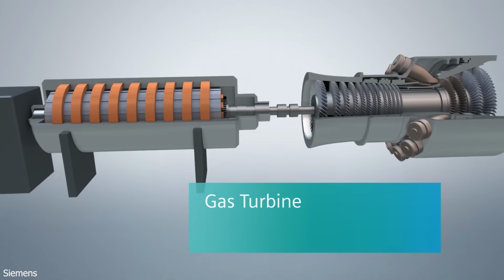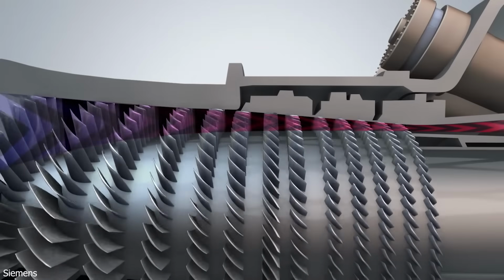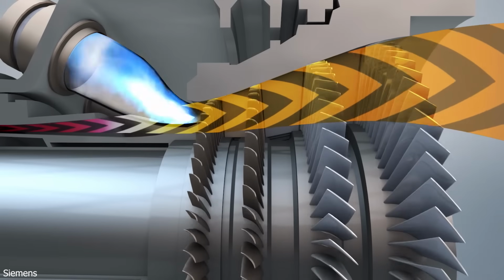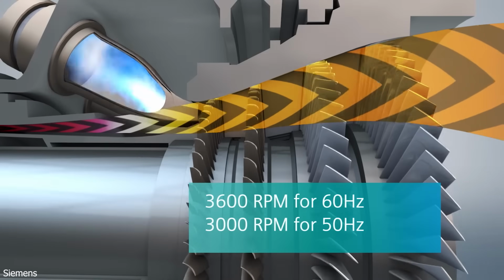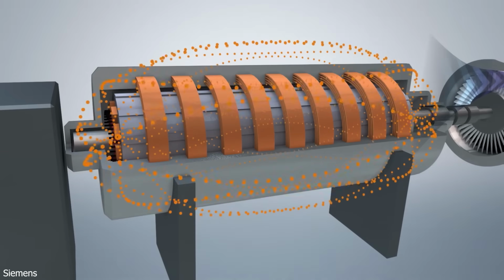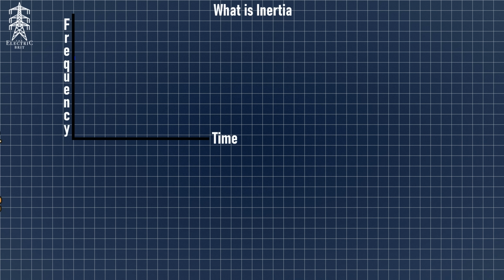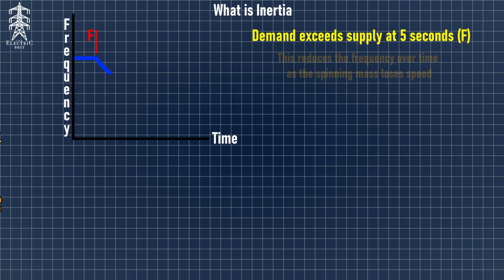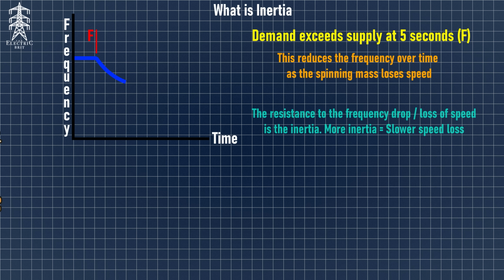By some neat physics, traditional synchronous generation, or simply turbines, are naturally grid forming. This is because the turbine frequency is set by its speed, and the speed is controlled by the plant operators. Because of its spin and mass, it has inertia, so when the load changes, the inertia tries to resist the load change, keeping the system stable. So how does grid forming work?